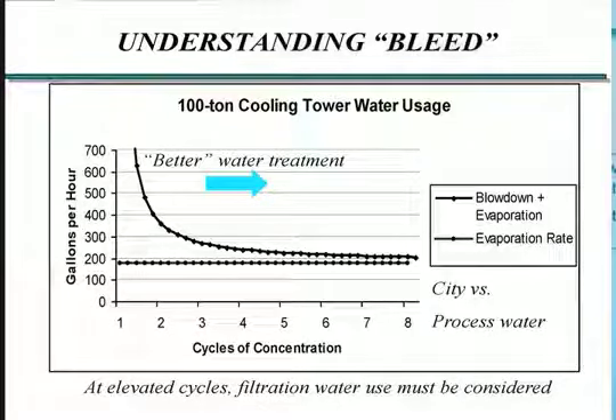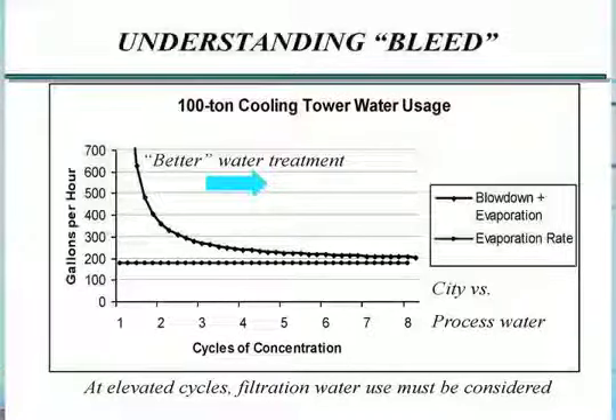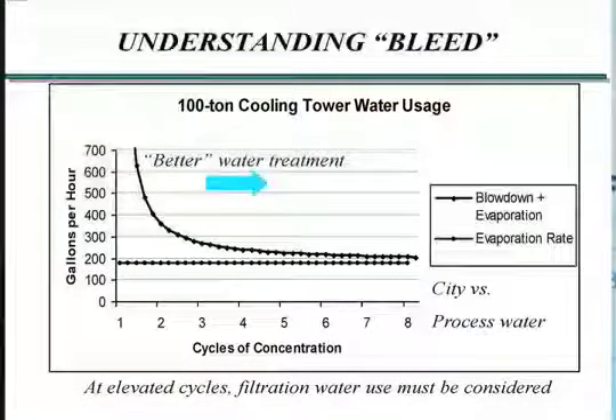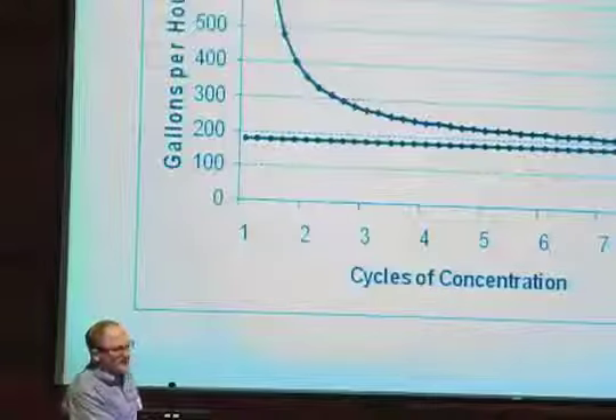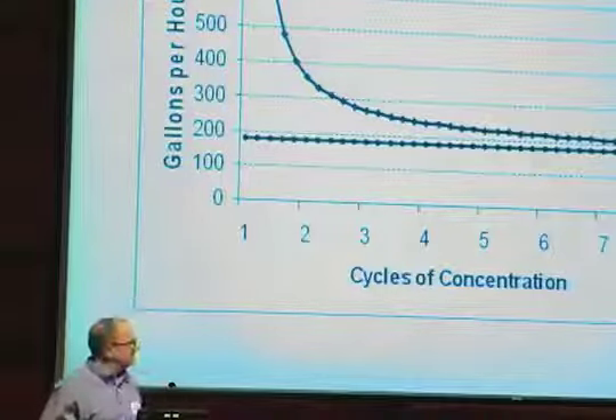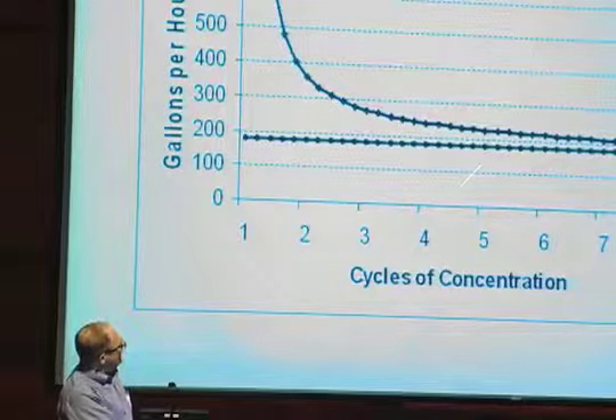This is the amount of water that in this case, a 100-ton cooling tower uses at different cycles of concentration. And as you increase cycles of concentration, obviously your overall water use, which is the top line, decreases. As you increase your cycles of concentration, the additional savings gets less and less and less. And you sort of approach asymptotically this line down here, which is the overall evaporation required to do the 100 tons of cooling we're talking about here. So in a general sense, to kind of step out of the whole issue of water treatment and filtration, this amount of water use right there is what is required by your heat load.